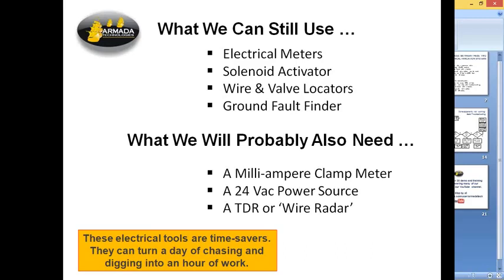But when we get to two-wire systems, there are a couple extra items you need to know about, and I've got a picture of some of these here as we go forward. A milliamp clamp meter is something that's critical, especially since we're really concerned about the splices in the system. We need to be able to find out what's going on in the system's control wiring without opening splices. So a clamp meter is the right answer here, because it clips over the wire without having to do any kind of wire skinning or opening of splices, and furthermore, it has to be a very sensitive RMS clamp meter that allows you to read the tiny currents that are flowing through these two-wire systems.